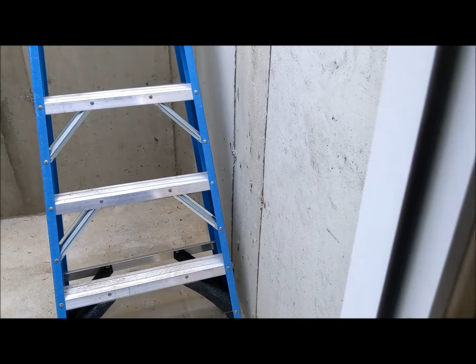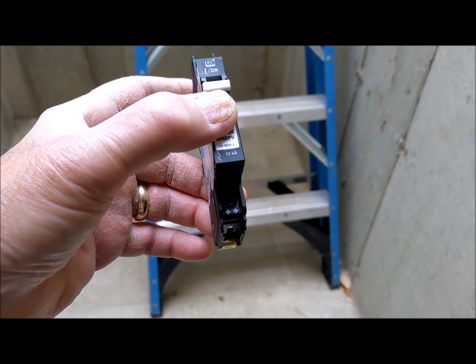Also, my wire stripper only goes down to 12 gauge wire. So these are DC circuit breakers, and the one thing to remember when doing this is that they have a polarity to them. The positive needs to come in one side, and if you take a close look at the circuit breaker...